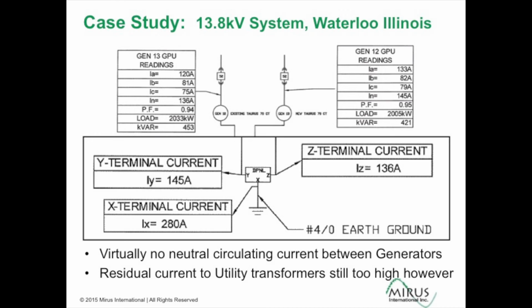So essentially, all of the current that's coming from these generators was going through the X terminal and back through the ground. There was no circulating currents between the two generators. Problem is, 280 amps is still a high level of return neutral current. The reason that neutral current was returning was going through the utility transformer neutral to ground connections, which we weren't aware of when they approached us for the application.